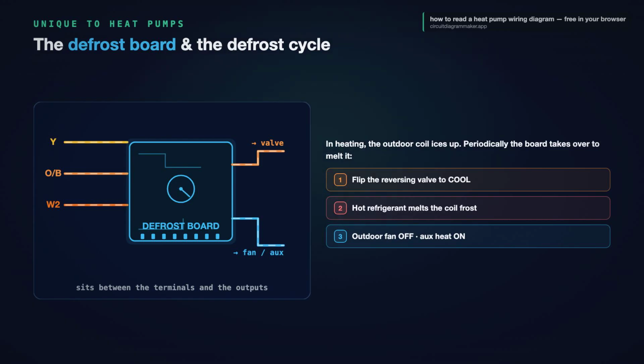At the same time, it shuts off the outdoor fan and turns on your auxiliary heat, so you're not blowing cold air indoors. On the diagram, the defrost board sits between the low-voltage terminals and the outputs, tapping into Y, the reversing valve, the outdoor fan, and W2. When a heat pump briefly steams outside in winter, that is the defrost cycle you just read on the page.